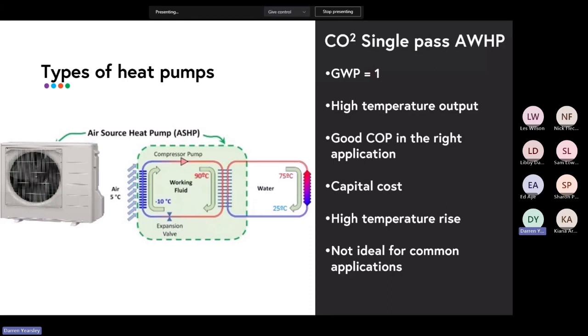So much so that typically in these systems, you'll see that a CO2 heat pump will be partnered with electric backups. So part of that is because of this compressing of the COP across the appliance and the stress it creates on the compressor when it's not operating in single pass anymore. And part of it is because they don't do very well in partial load. So if you're just trying to recover ring main losses, a CO2 heat pump doesn't do that very well. So typically they'll do that with an electric backup.